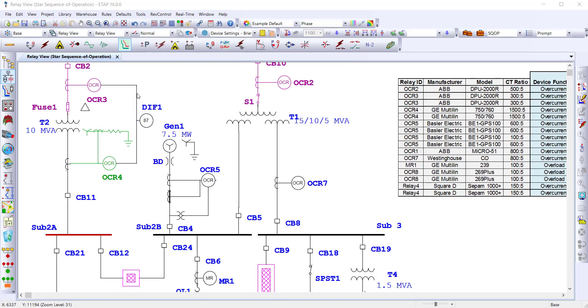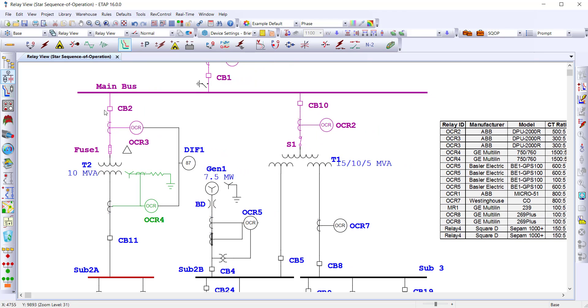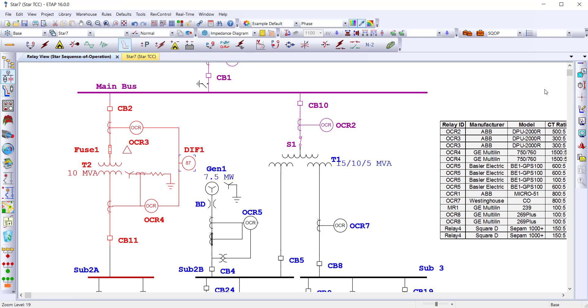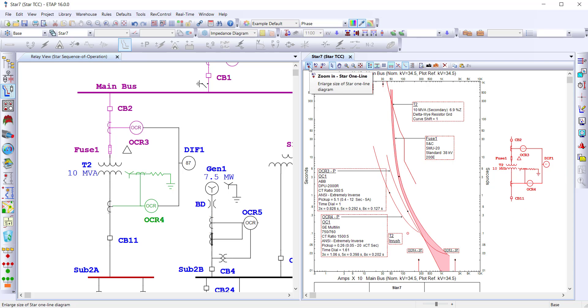There are multiple ways to create a TCC view. One of the first ways we will discuss is a simple selection of the elements required in the coordination study, then selecting to create a star view. We can select to show settings or not show settings on any of the protective devices in the TCC view, and a replication of the one-line diagram is created, which can be enlarged or reduced.